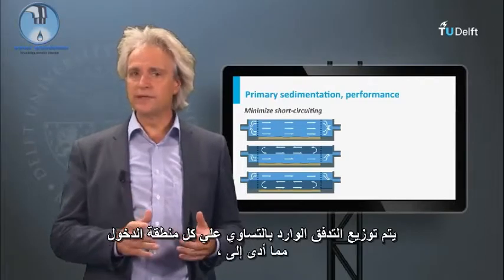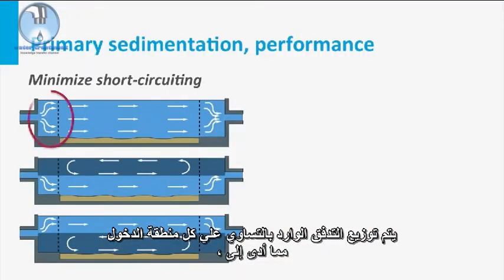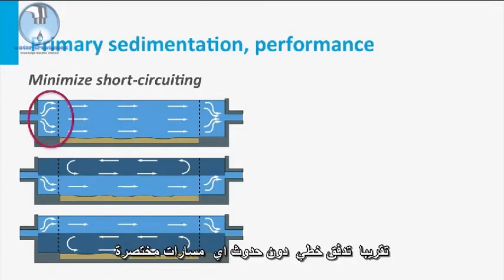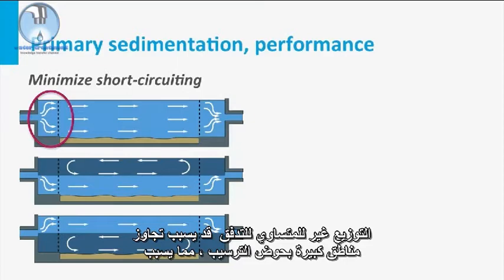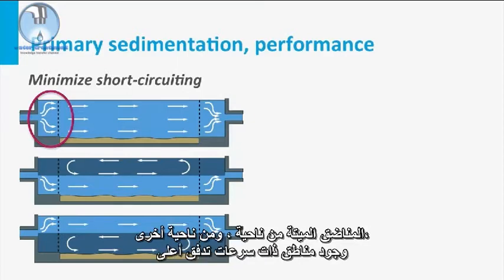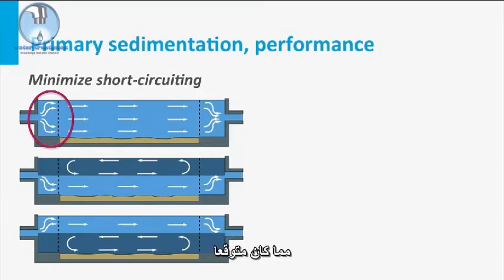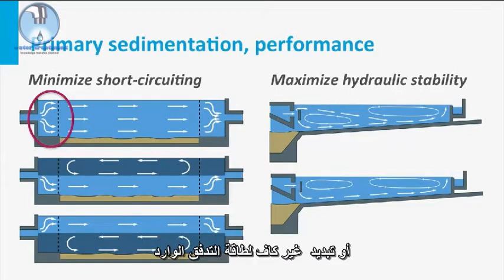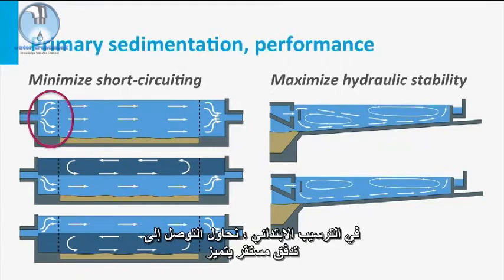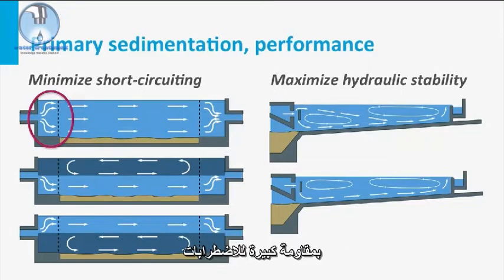Most ideally, the influent is distributed equally over the entire inlet area, resulting in a more or less laminar flow without any areas of hydraulic short-circuiting. Inadequate flow distribution may bypass large areas of the clarifier, resulting on the one hand in dead spaces, and on the other hand in areas with much higher flow velocities than foreseen. Also, circular tanks may develop unstable flow regimes as a result of inadequate flow distribution or improper energy dissipation of the incoming flow. In a primary clarifier, we try to reach a stable flow regime characterized by a high resistance to flow disturbances.